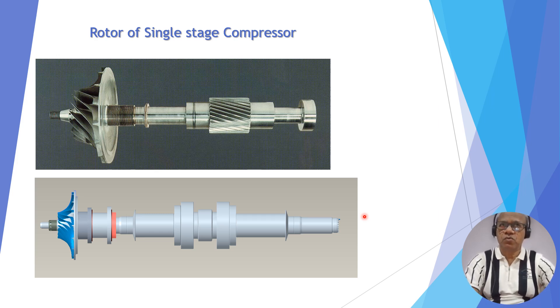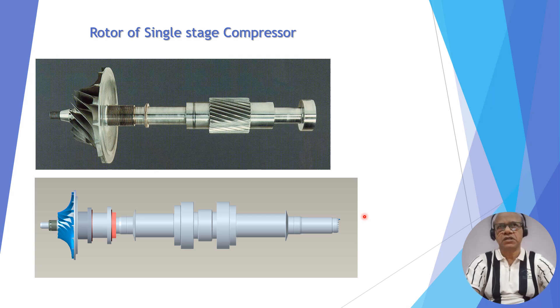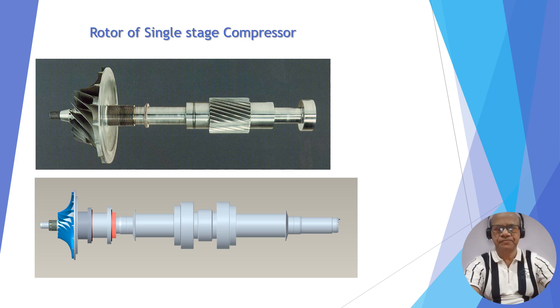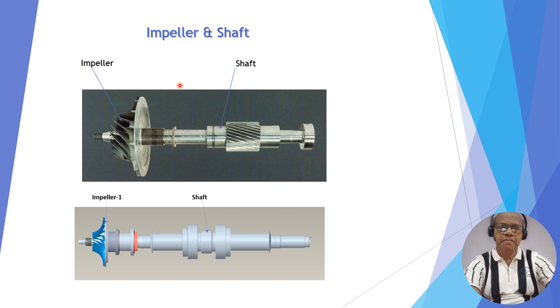The question is: why does the rotor have axial thrust? It is because of pressure variation — because of the change in pressure, the force is also changing. So what are the pressures contributing to axial thrust, or in turn, what are the axial forces that cause the rotor to thrust in a particular direction? The impeller is sometimes called a wheel, but in compressors it is normally called an impeller, and this is the shaft. All rotating components together are called the rotor.